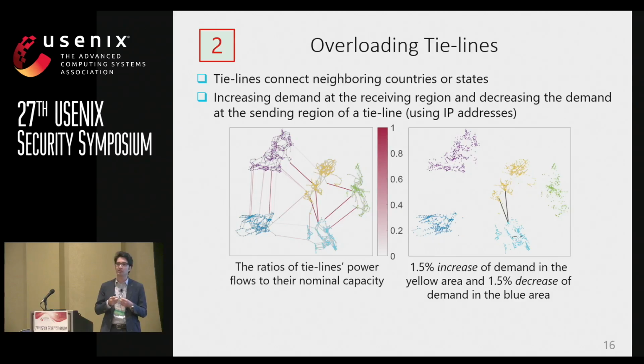Tie lines are usually high capacity lines that connect neighboring states or neighboring countries, and they are usually carrying a large amount of power flow that is exported from a state or imported. An attacker can cause failures in these tie lines by increasing the demand at the receiving end of these tie lines and decreasing the demand at the sending end. We look at a hypothetical scenario which connects 5 countries, for example, and we observe that by increasing the demand by 1.5% in the yellow area and decreasing the demand by 1.5% in the blue area, we can cause line failures in both of these tie lines.